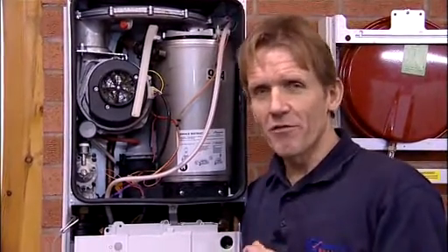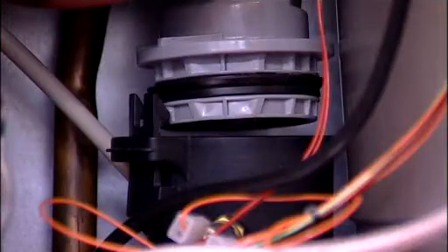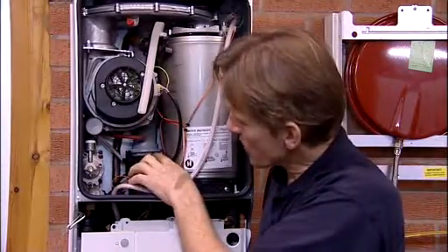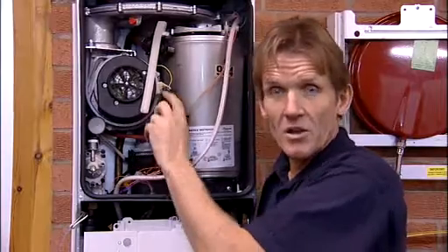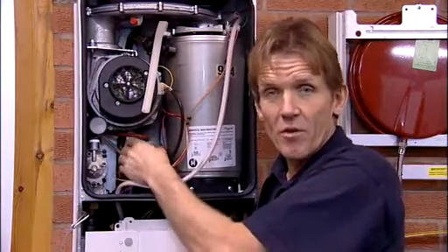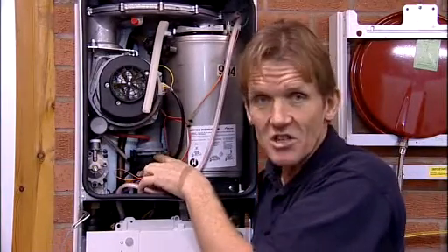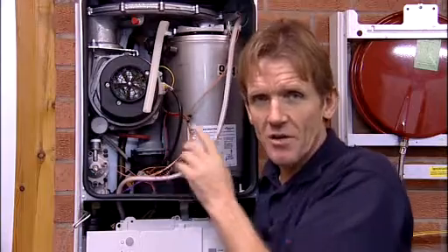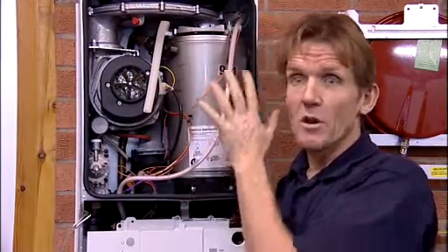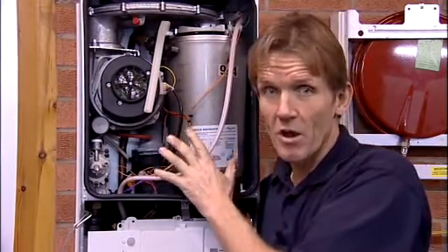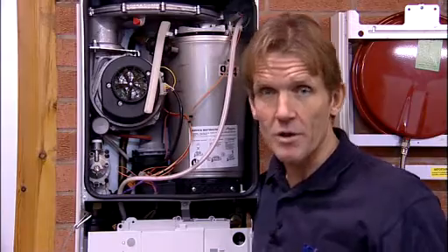Now we all know that when you're fitting flues you can sometimes get a little bit of a tussle with them, and it can cause the internal connection to come adrift, to come out of its socket. There's one seal at the bottom and there's one seal at the top. Before you fire the boiler up, just check that these are actually in place, because if they're not, what you sometimes find is the boiler will only work when the front cover's removed or you get a lockout fault.